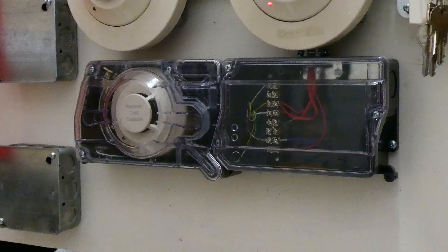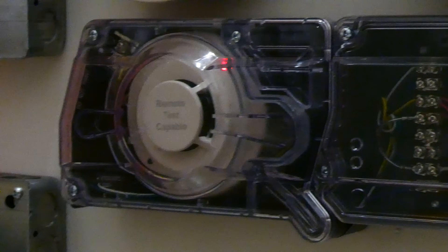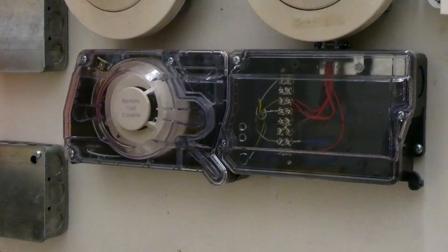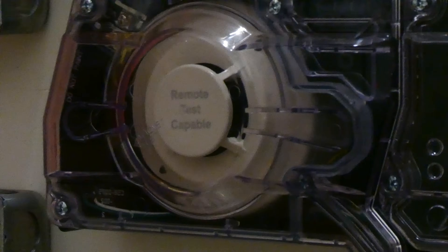So let's demonstrate that. This is what we're going to be testing first. This right here is a D355PL Fire-Lite duct detector. They have special smoke detectors that mount on the sides of air ducts and they will sense the air that moves through the air duct for smoke. Sometimes it picks up dust and accidentally sets off the alarm, but if it thinks it sees smoke then it will sound the alarm. So that's what we're going to be demonstrating today.